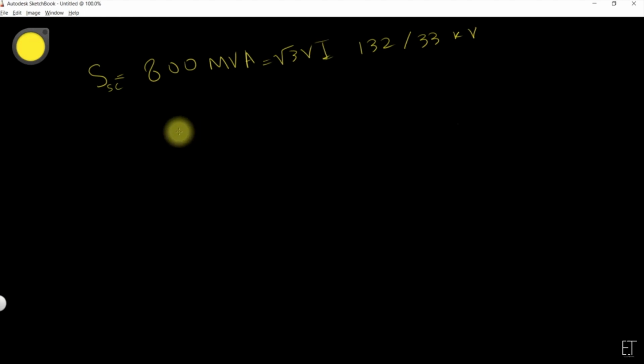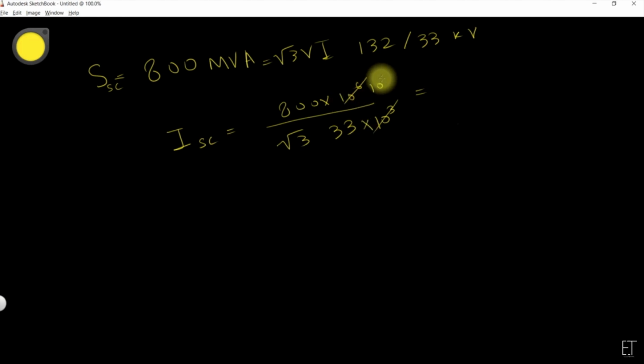To calculate the short circuit current I at the low voltage side, it will be equal to 800 into 10 raised to power 6 divided by √3 divided by 33 into 10 raised to power 3. That is 10 raised to power 3, so it will be 800 multiplied by 1000 divided by 1.732 divided by 33 divided by 1000.